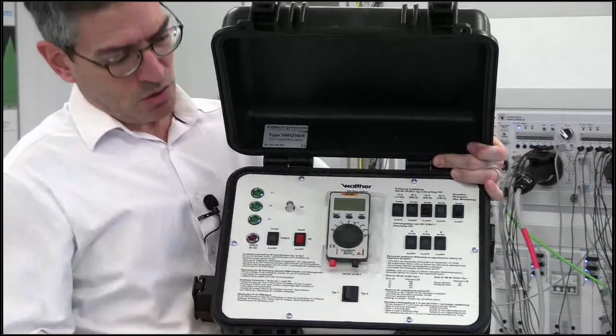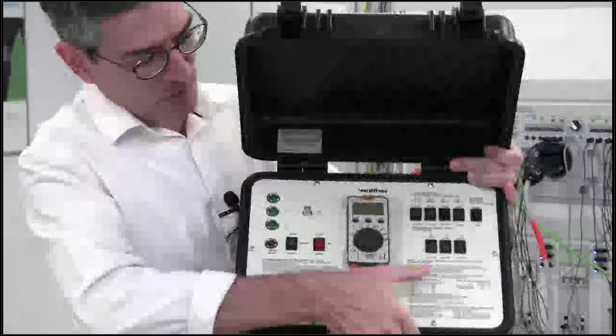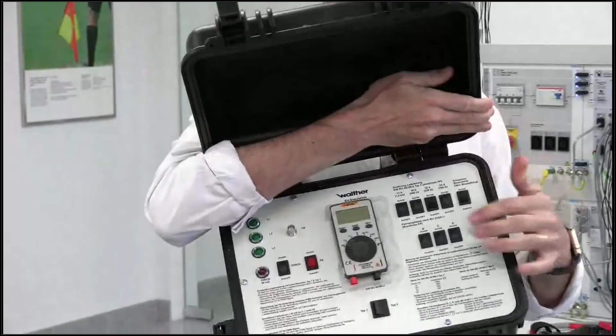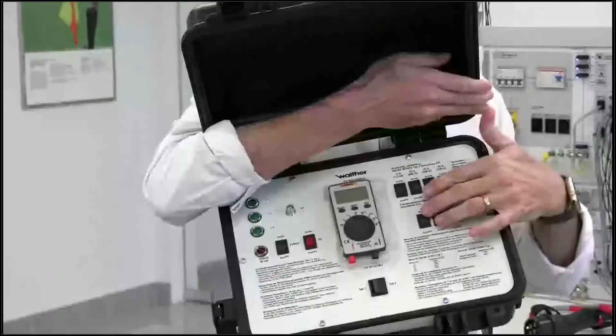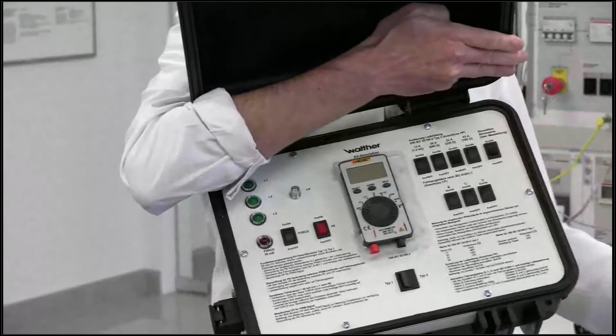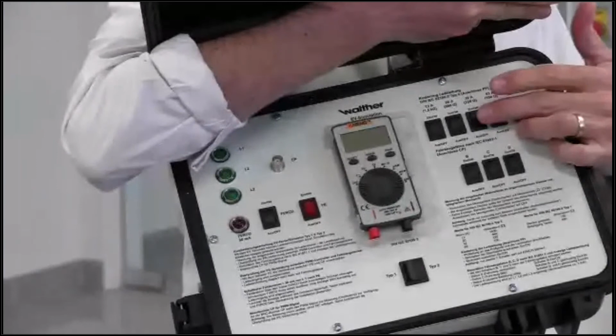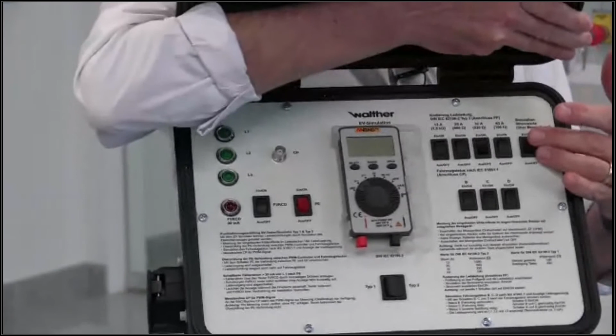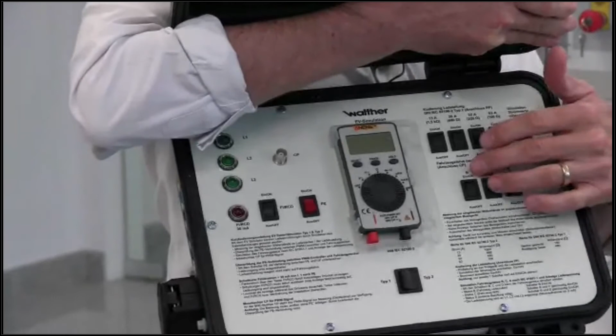So we can simulate the protective earth here, and we can indicate the ampacity of the cable that we use. The connected cable has a different capacity in terms of current it can carry, but here we can emulate different ampacity for these cables simply with these switches to see how the charging station reacts to being connected to a cable of one capacity or another.